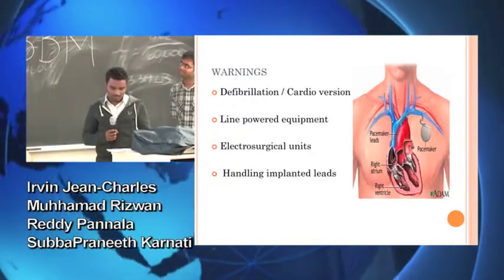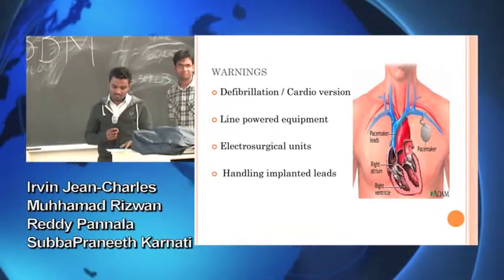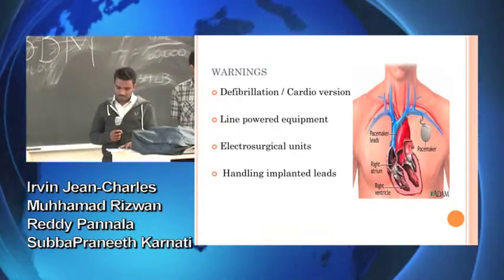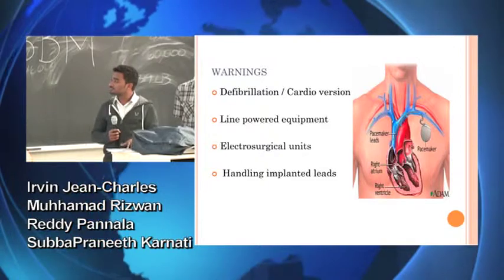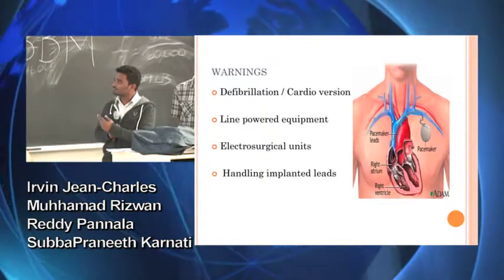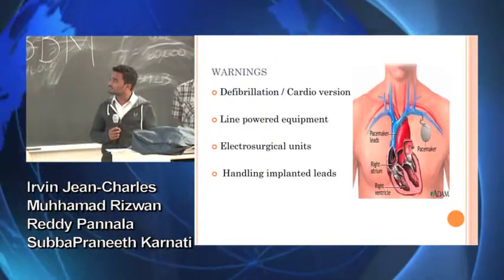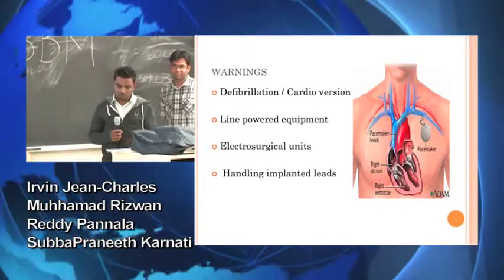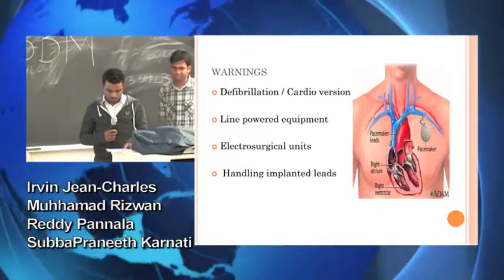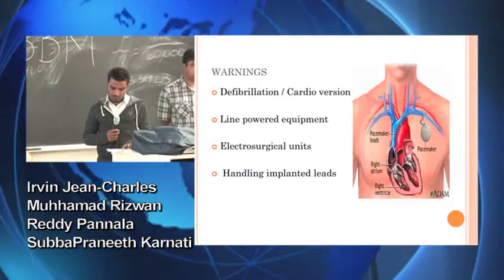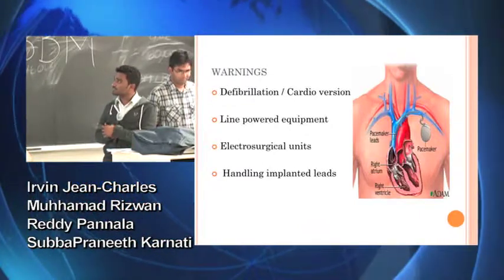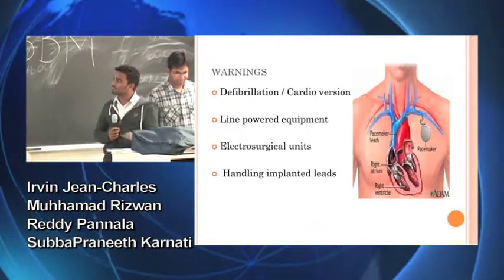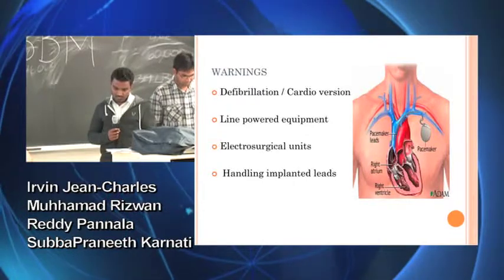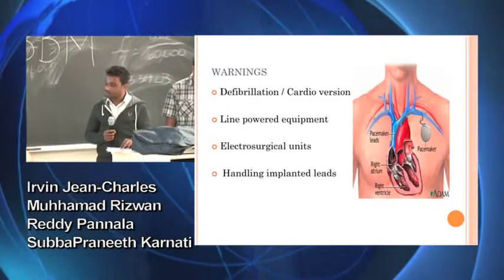slow heartbeat. And defibrillation is a process which involves 360 watt-seconds of power. Once it has been tested in the lab on the pacemaker, it works in an exact way, and it doesn't lose any property. So whenever possible, it is better to disconnect the pacemaker and then test the pacemaker. That's the reason why I mentioned defibrillation and cardioversion.